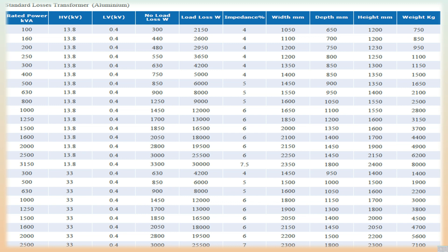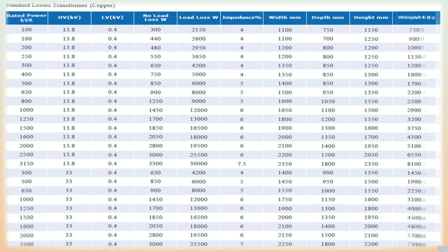Magnetic Circuits: The structure of the magnetic circuit uses a three-legs construction with step-lap stacking. It is made from cold-rolled grain-oriented silicon steel strip (CRGO), where each strip — 0.23, 0.27, or 0.30 millimeters thick — is insulated on both sides.